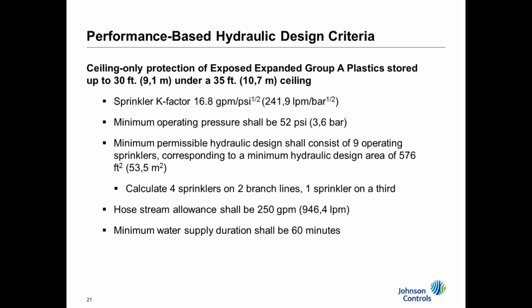So for an application overview, I just want to walk through this. What you're going to be dealing with are performance-based hydraulics designs. For the first application that we're doing, we have UL listings for a 35-foot building with 30 foot of exposed expanded Group A plastics using a 16.8 K factor sprinkler at 52 PSI. The minimum permissible hydraulics we're going to allow will be 9 operating sprinklers, and we're going to calculate 4 sprinklers on each of 2 branch lines and 1 on a 3rd line, because we found through testing that in no case did we ever pass a length of branch line of more than 4 sprinklers, which is really good. And we're only going to do 60 minutes. So that's how we're going to set up our criteria.